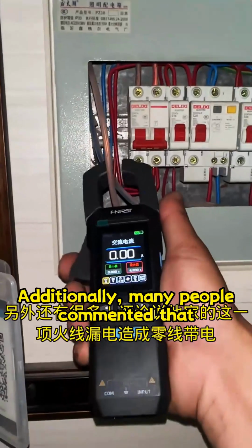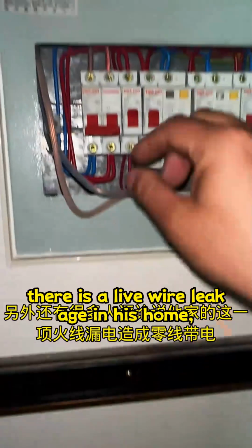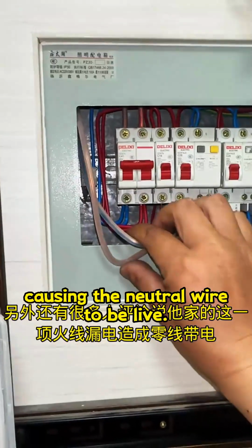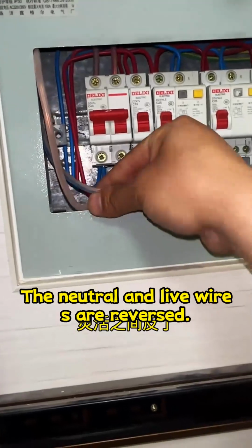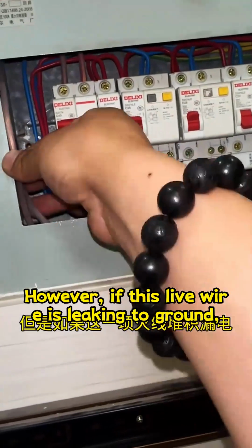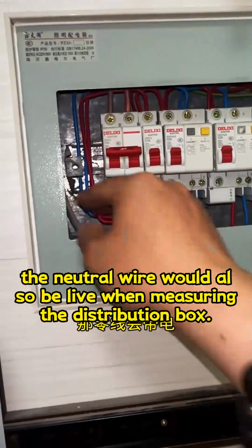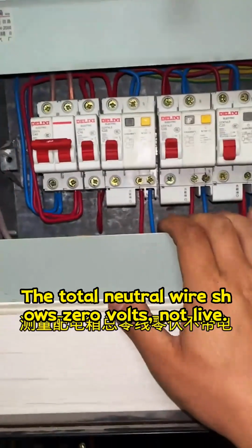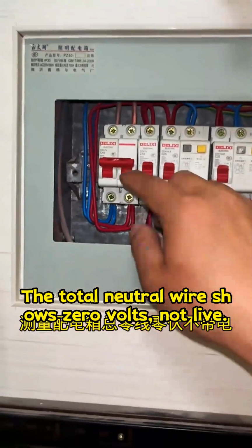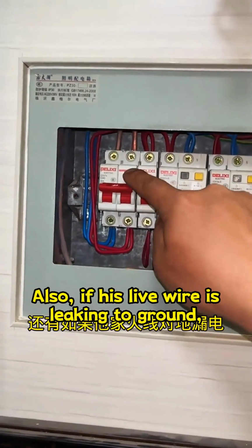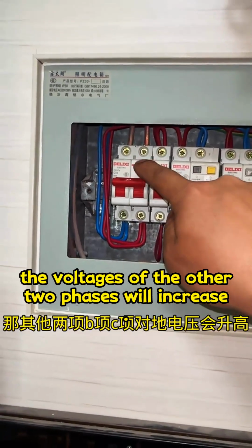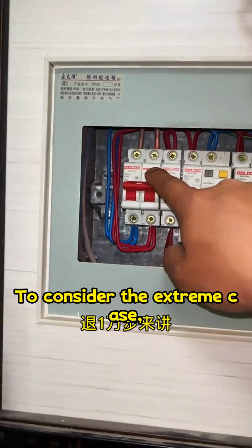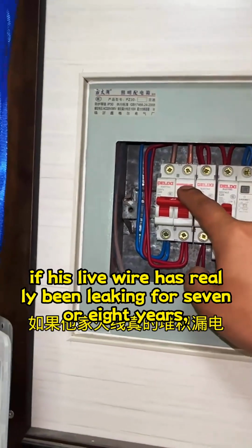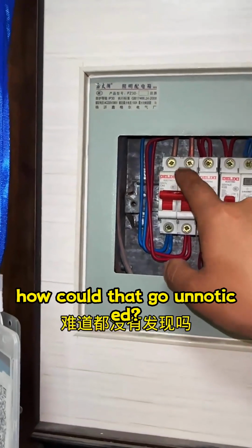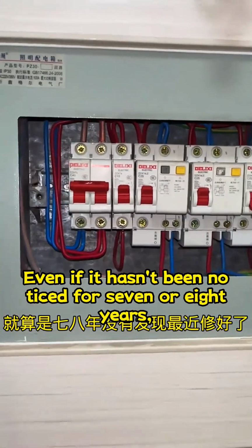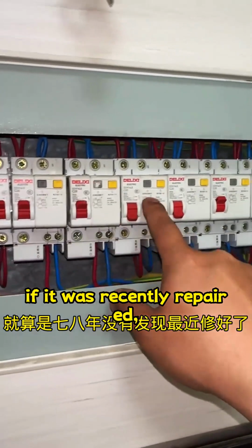Additionally, many people commented that there is a live wire leakage in his home, causing the neutral wire to be live. The neutral and live wires are reversed. However, if this live wire is leaking to ground, the neutral wire would also be live when measuring the distribution box. The total neutral wire shows 0 volts, not live. Also, if his live wire is leaking to ground, the voltages of the other two phases will increase. To consider the extreme case, if his live wire has really been leaking for 7 or 8 years, how could that go unnoticed?